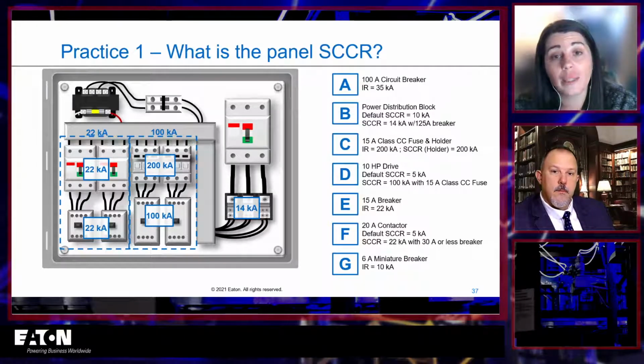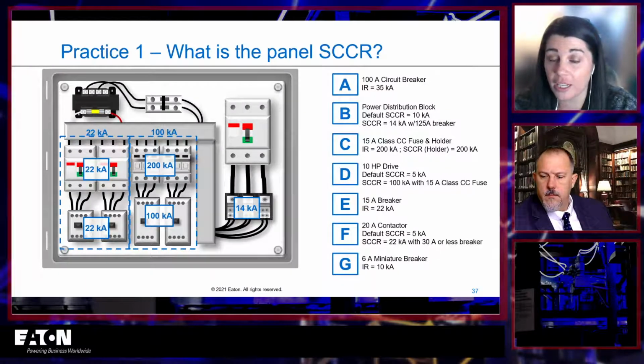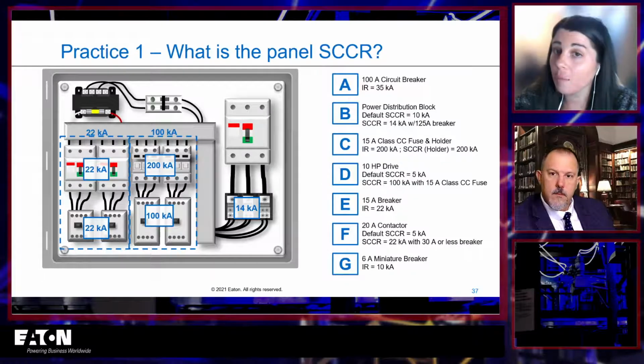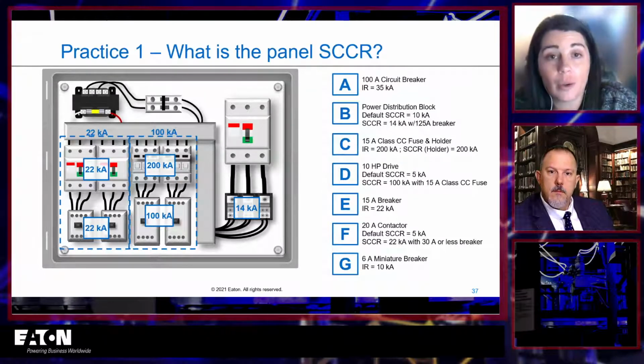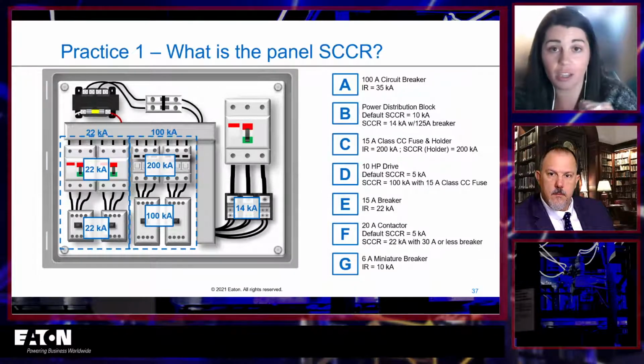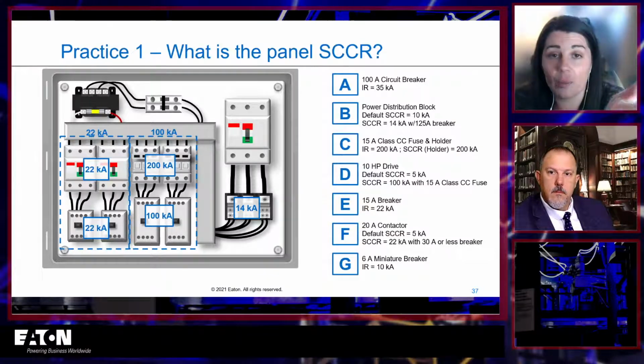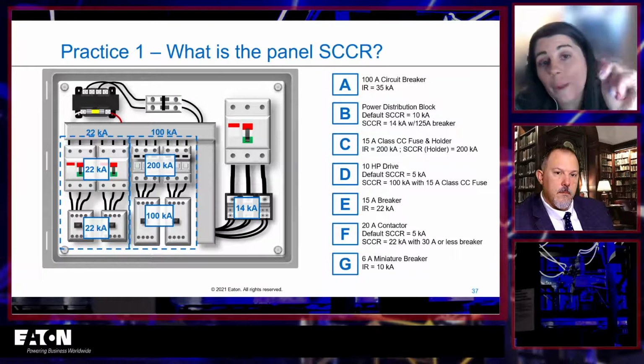And then last but not least, I have to identify all of the interrupting ratings in my panel. So anything in my power circuit that has an interrupting rating, I want to make sure those are labeled. My branches are already taken care of. Obviously, I want to look at this main breaker. This main breaker has an interrupting rating of 35, so I put that on there.